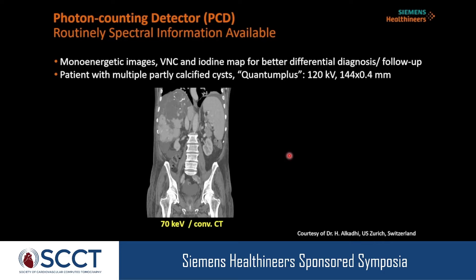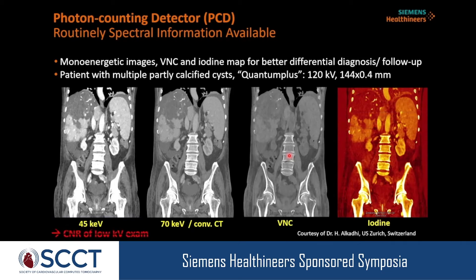Here's what can be done with the data: a patient with a partly calcified lesion acquired at 120 kV. We see a 70 keV image representing a conventional CT. You can calculate a virtual non-contrast image with iodine removed algorithmically, calculate a pure iodine distribution image in quantitative fashion, and calculate mono-energetic images — which are the standard output of a photon counting system. Going to a low value of 45 keV demonstrates substantially increased iodine CNR, making low kV scanning obsolete since you can achieve this virtually from 120 kV data.